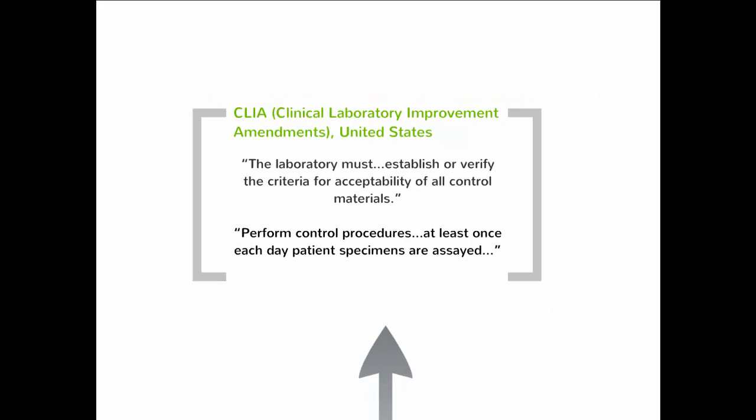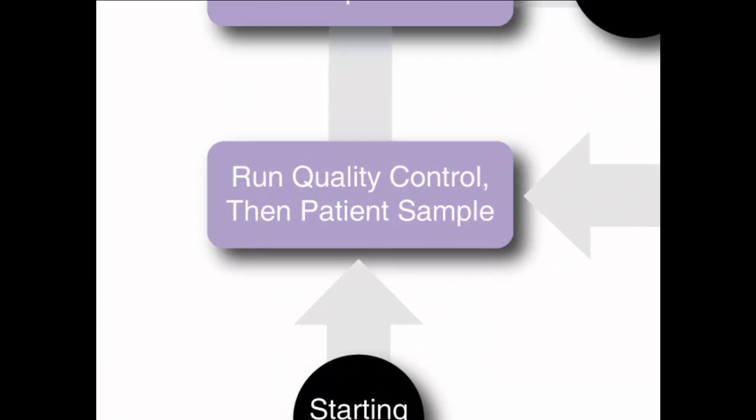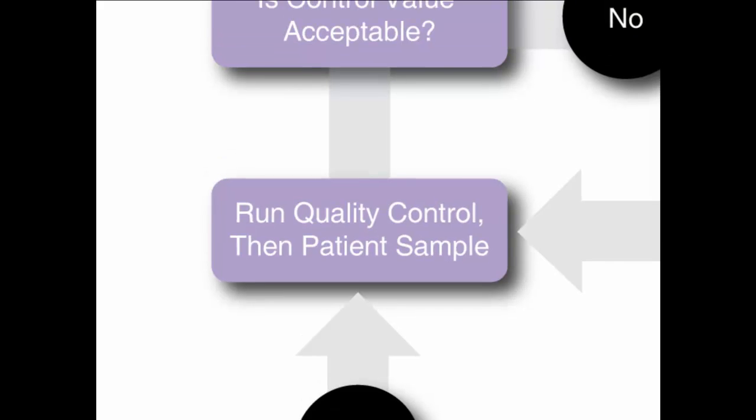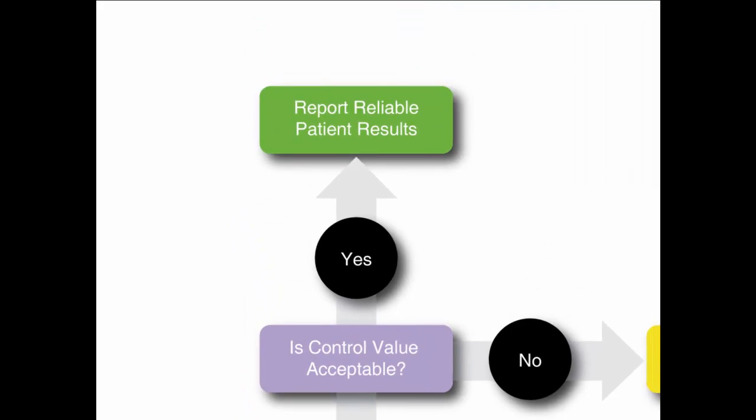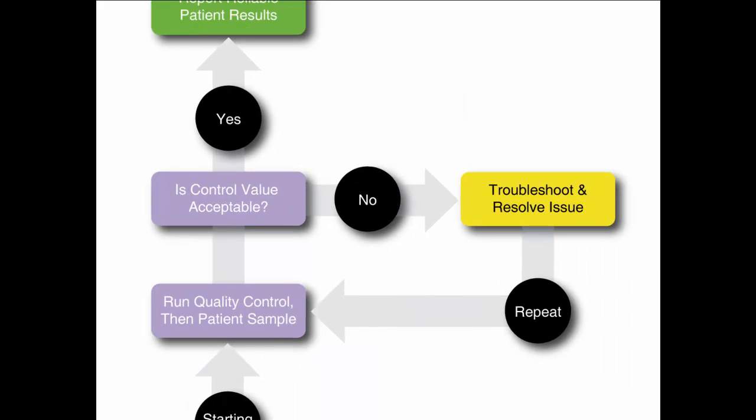The different worldwide standards might leave some laboratories looking for a starting point. Start by running a quality control before running patient samples. Determine if the control value is acceptable. If it is, you can report reliable patient results. If it isn't, troubleshoot, resolve the issue, and repeat the test.